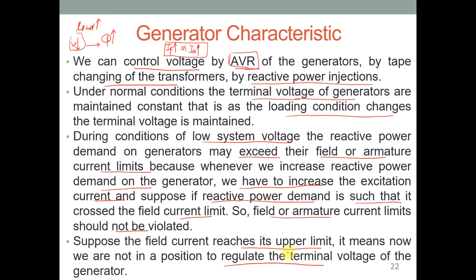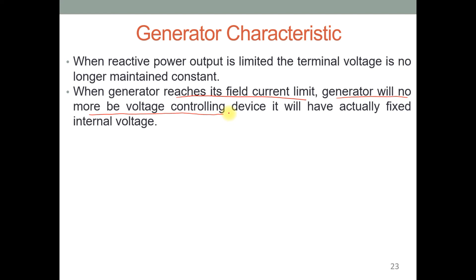So when the reactive power output is limited, the generator terminal voltage is no longer maintained constant. Clear? So when the generator reaches its field current limit, the generator will no more be a voltage controlled device. That means it will act as a constant voltage source. Clear? Just understand the word.